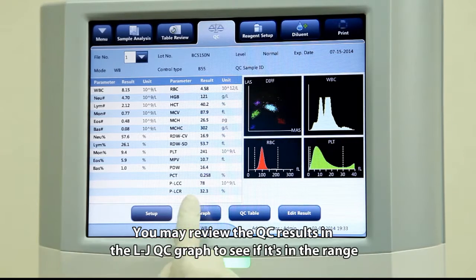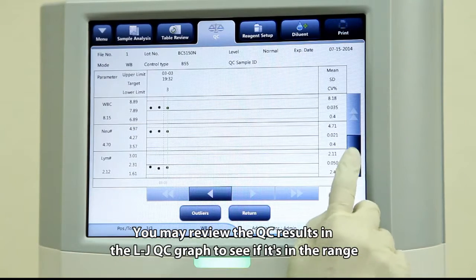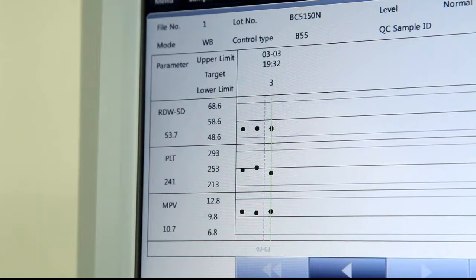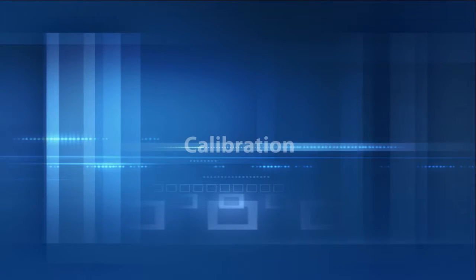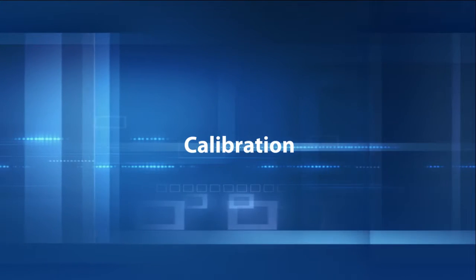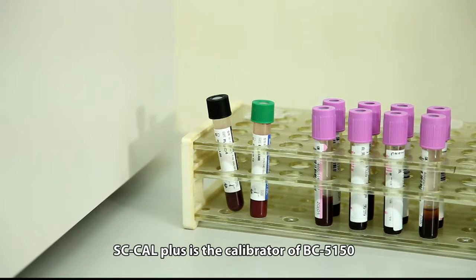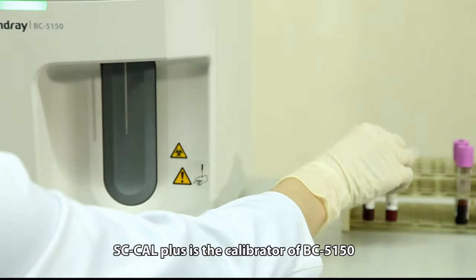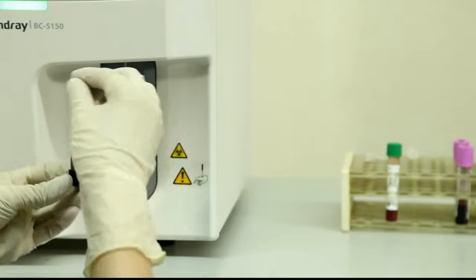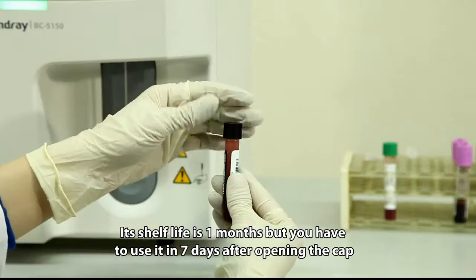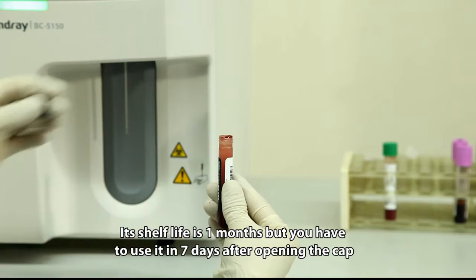You may review the QC results in the LJ QC graph to see if they are in the range. SC-Cal Plus is the calibrator of BC5150. Its shelf life is 1 month, but you have to use it within 7 days after opening the cap.